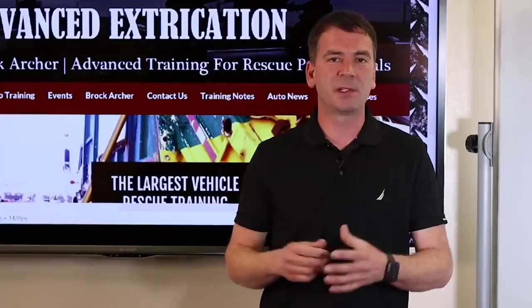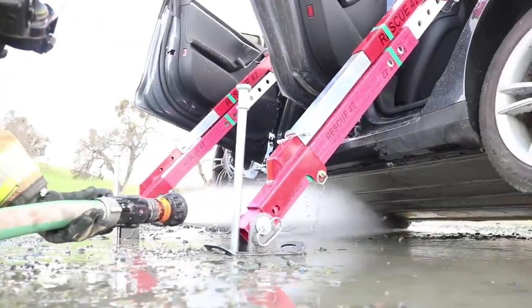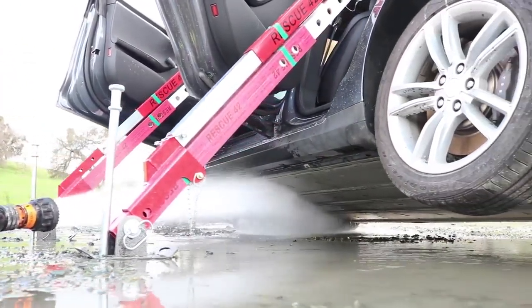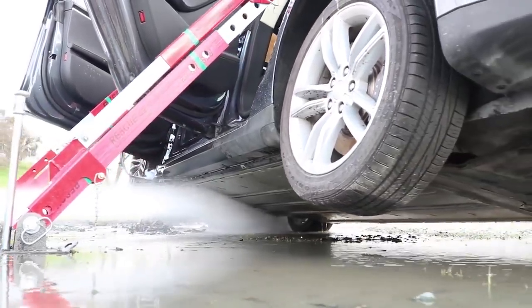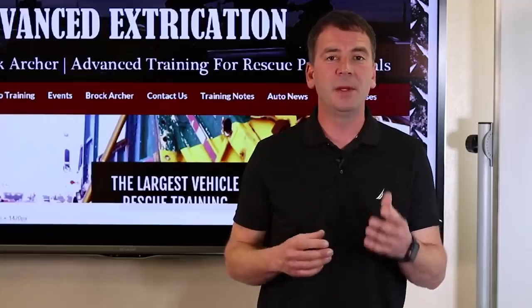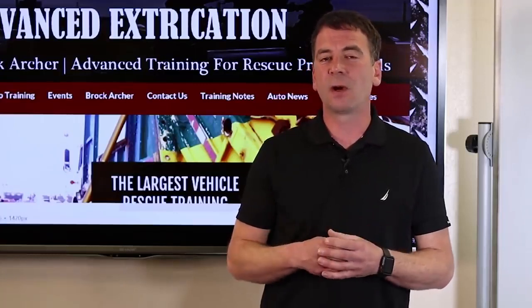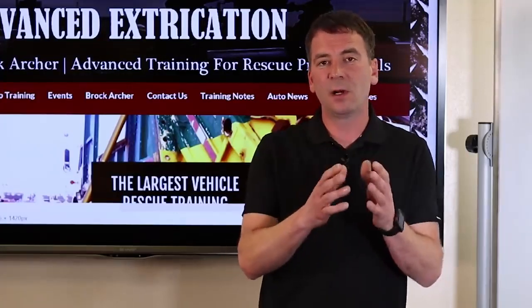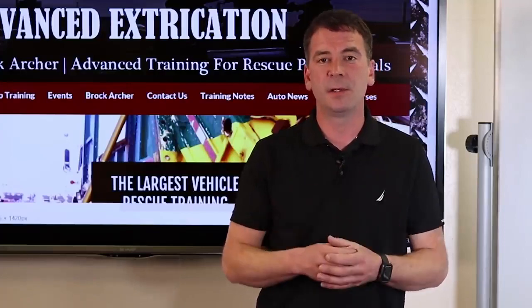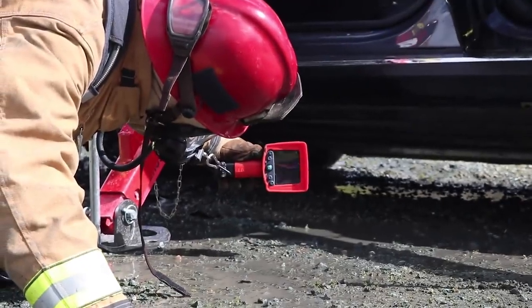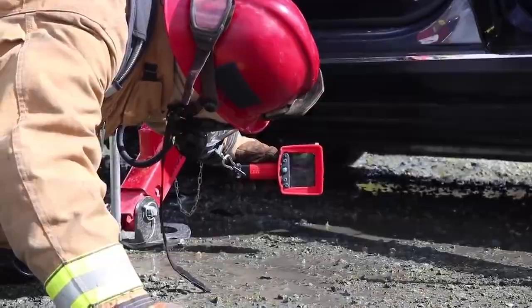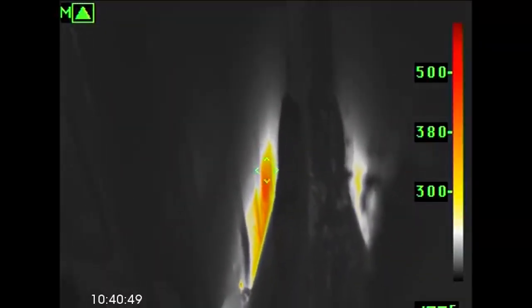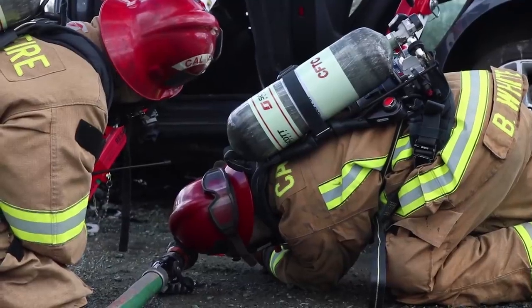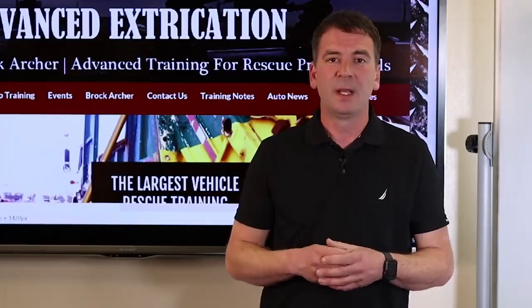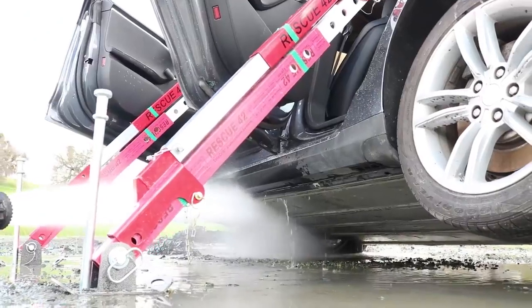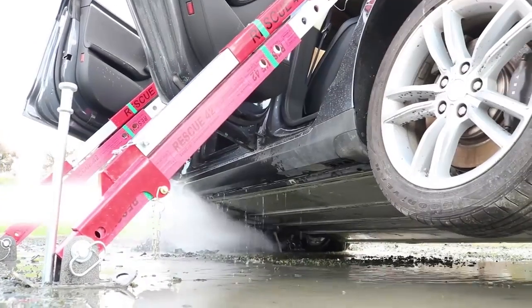Cooling the battery is very simple. A long, continuous stream of water applied to the case of the battery is the most effective way to reduce the temperature within the battery and limit thermal runaway. The hose stream should be placed on an area of the battery where heat is determined, using a thermal imaging camera or by visually watching for areas where smoke and steam are venting. That application of water should take place for an extended period of time and not be interrupted.